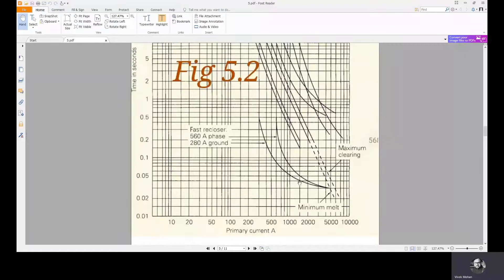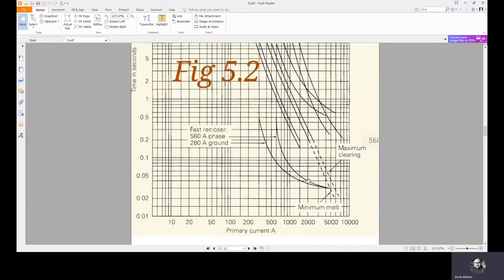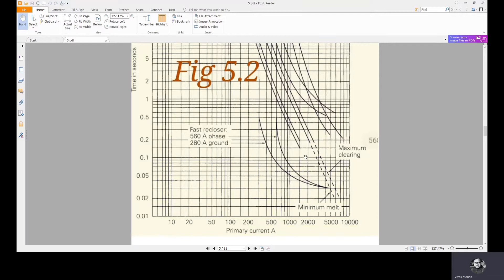For 1500 amps, the first event is the same: at 0.05 seconds we have the curve corresponding to the 560 amp fast recloser. So the fast recloser at 560 amps operates. Then after half a second, when it closes, it closes into the permanent fault — not into a cleared temporary fault. Rather, it closes into the permanent fault again after half a second. So it again opens — this is the second fast recloser. Then in the second time, it recloses after a two-second delay.